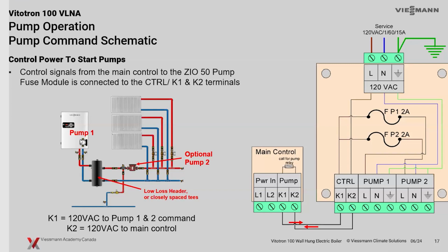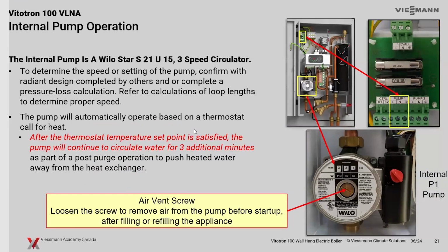So you get your built-in pump, kind of shown in the boiler here, and then a secondary pump, which we could use on pump 2. So we have a primary secondary system, and this is what we're kind of looking like. All right. So some pretty good little added functions on a small boiler with an extra relay output there. You don't have to buy another pump box for that, should you want to do a primary, secondary.